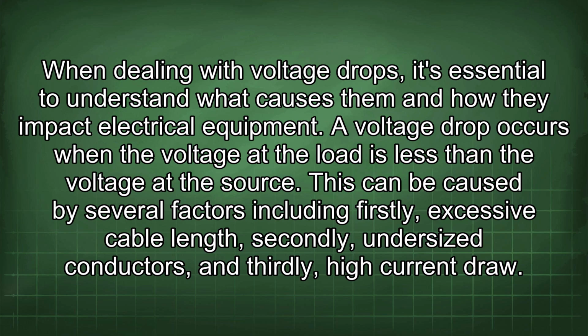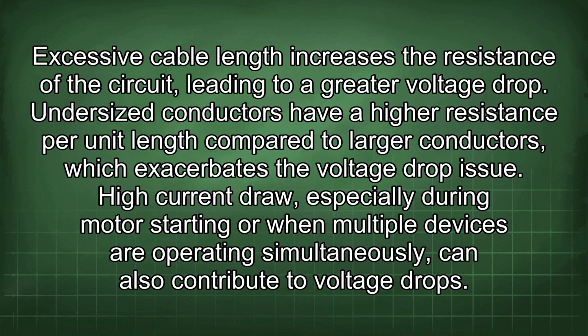A voltage drop occurs when the voltage at the load is less than the voltage at the source. This can be caused by several factors, including firstly, excessive cable length, secondly, undersized conductors, and thirdly, high current draw. Excessive cable length increases the resistance of the circuit, leading to a greater voltage drop. Undersized conductors have a higher resistance per unit length compared to larger conductors, which exacerbates the voltage drop issue. High current draw, especially during motor starting or when multiple devices are operating simultaneously, can also contribute to voltage drops.